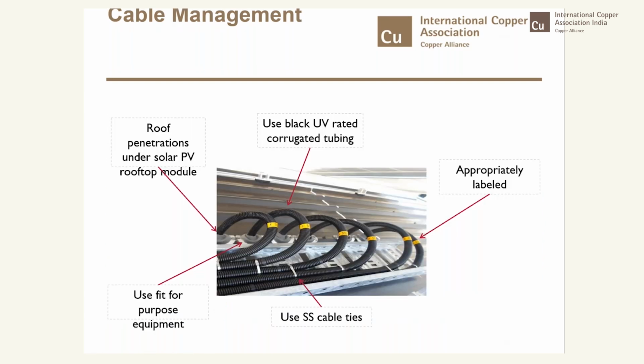Here on the module end, you can see how roof penetrations are done under the solar PV rooftop module, how the cables are taken downwards. The openings are well sealed with waterproofing compounds. And you can see in the picture, they have used stainless steel cable ties. And even the corrugated tubing, that black UV rated tubing, has to be used and needs to be appropriately labeled. Needless to say, it is not that the module alone will survive for 25 years.